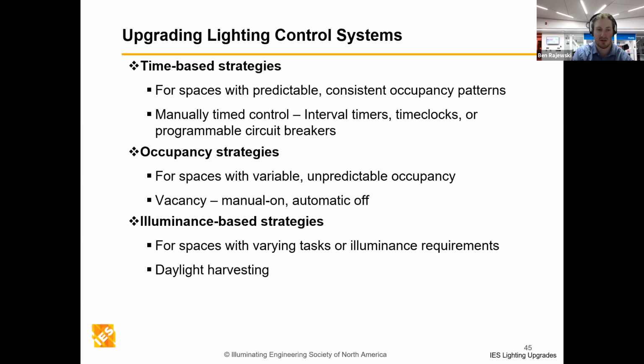Then you can go into occupancy strategies where you put occupancy sensors just on the ceiling spaces, in places like storage rooms and washrooms. You walk in, the lights go on and only stay on when people are actually in the space. Then you can add vacancy sensors in places like offices, where people manually turn their lights on and the lights go off once it detects no one's in the space. That's a third layer of control, and with vacancy sensors you can often also add dimming for another layer of control.